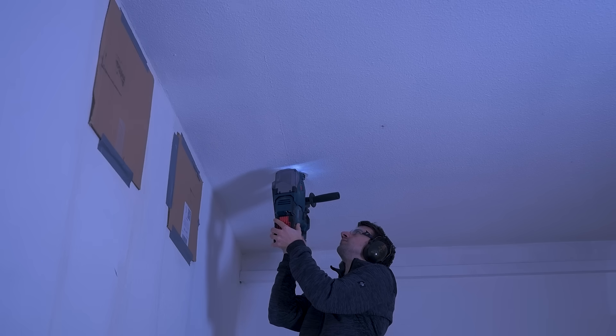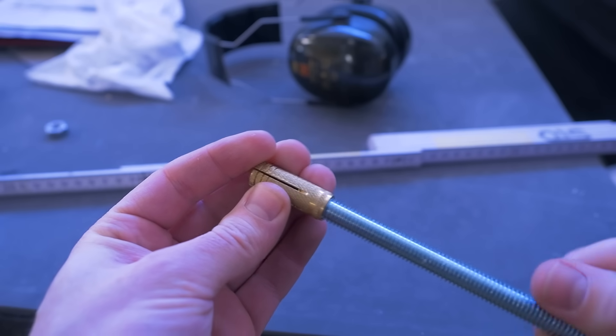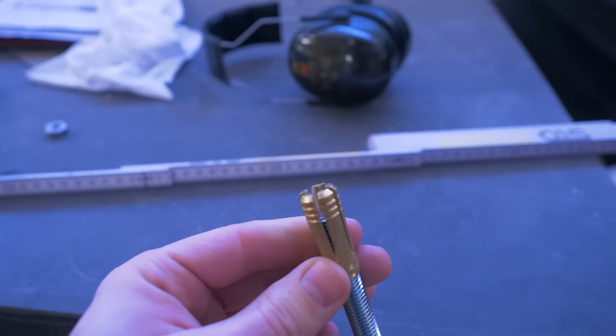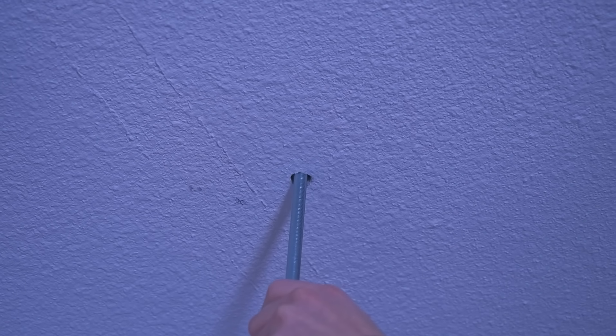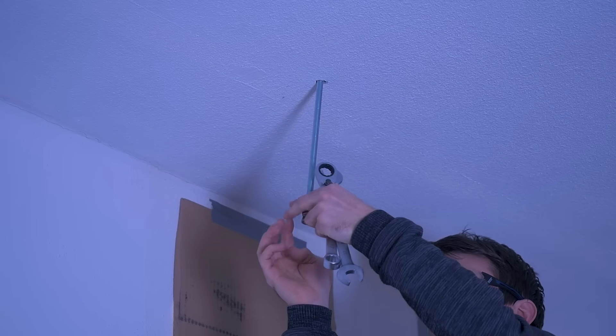Next, marking and drilling the holes for the threaded rod ceiling anchors. We used steel ones, which are actually required in case of a fire — plastic ones could melt and the machine would drop down. That doesn't happen with the steel ones.